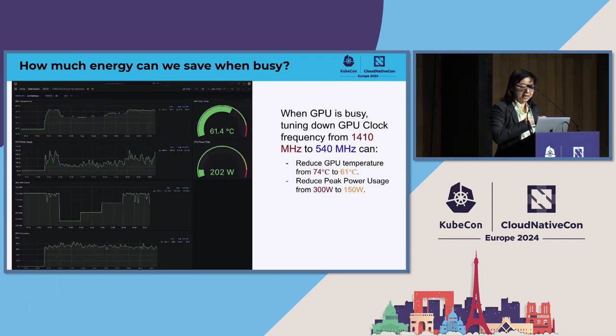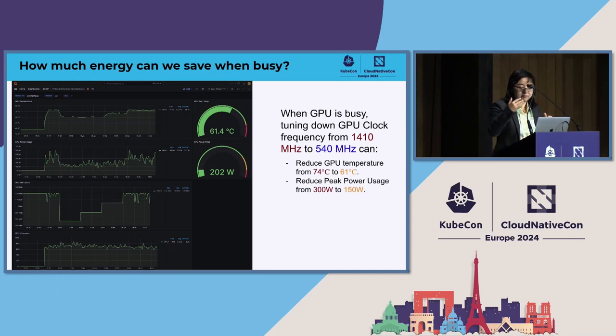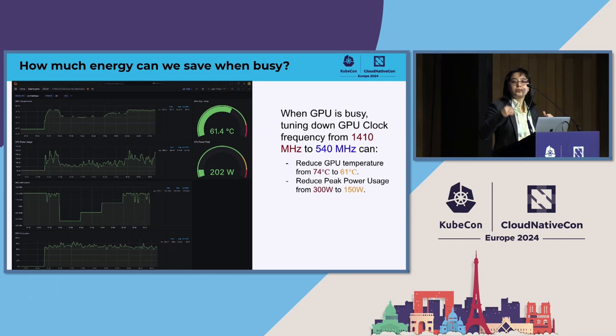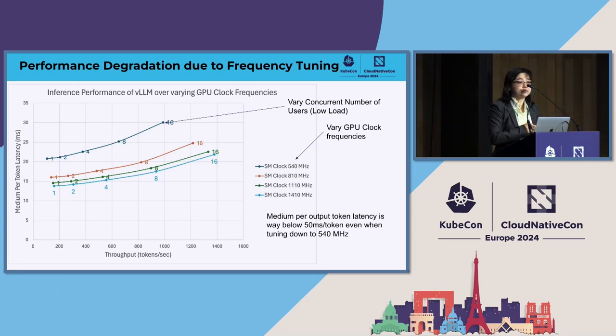Under load — sending 16 concurrent requests to the vLLM serving engine — tuning down the frequency reduced temperature from 74°C to 61°C. You can imagine how much cooling cost you can save. It also reduced peak power usage from 300 watts to 150 watts. But what happens to latency and throughput when we tune down frequency and requests come in?